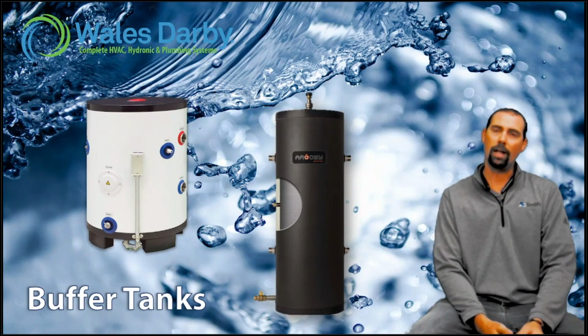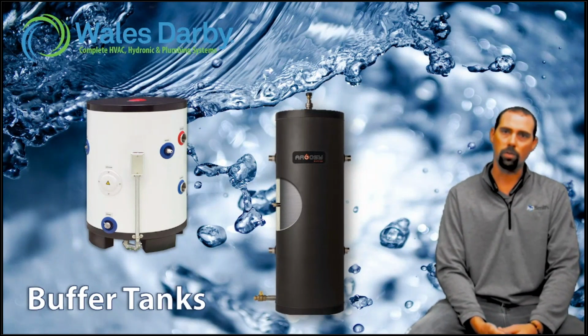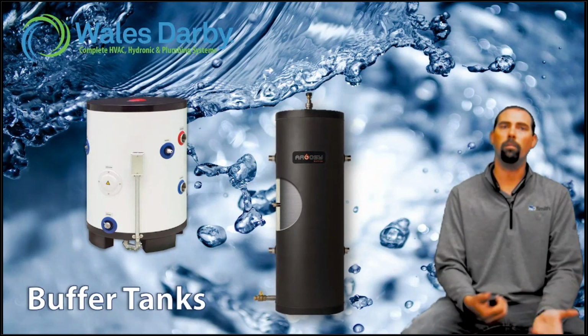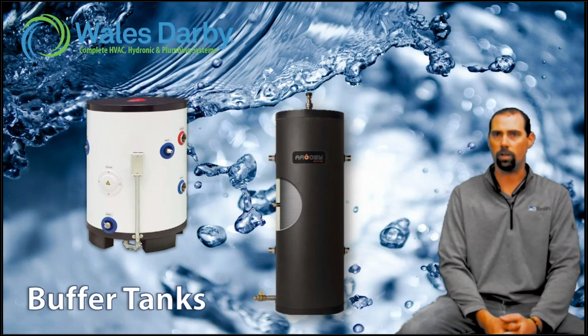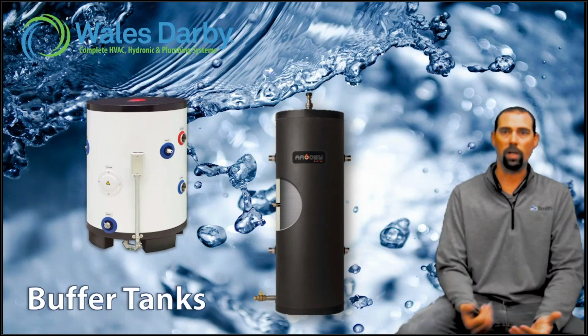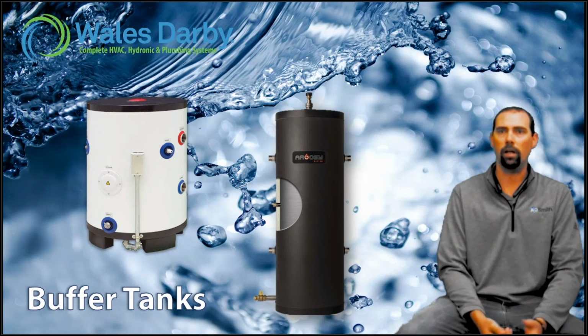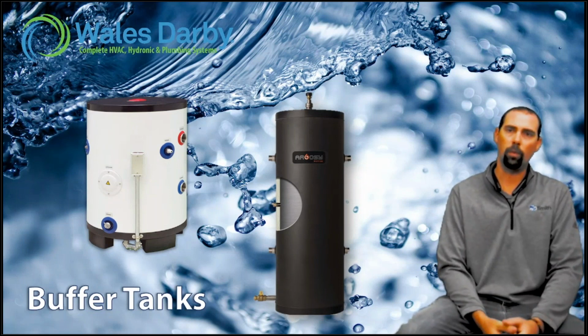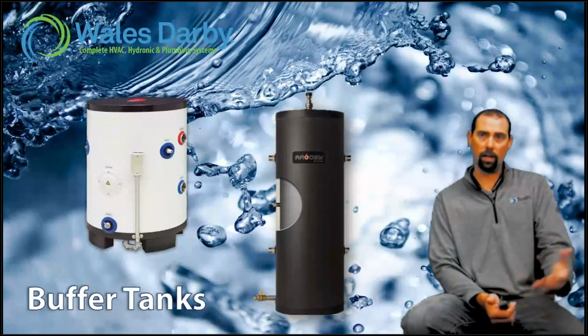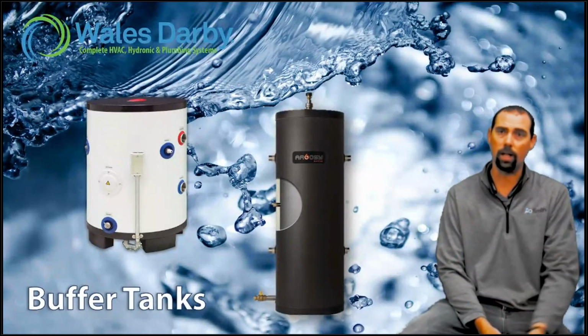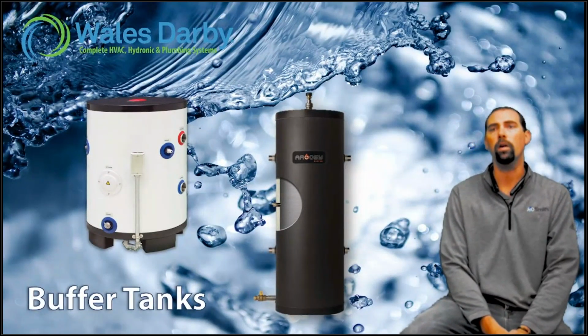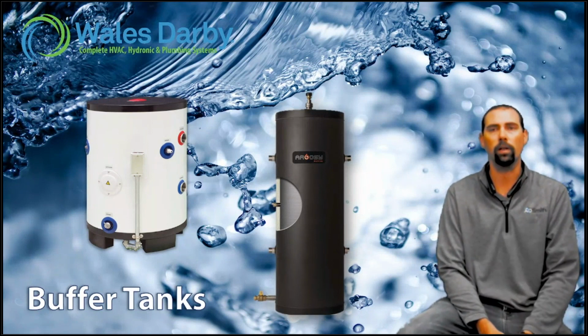One of the nice things with the new inverter technology is we don't have to go with as big a buffer tank in some residential applications, because we can ramp the outdoor unit down to match our loads. That's something we weren't able to do in older systems, so we had larger buffer tanks. Having more storage isn't a bad thing if you've got the space for it, but that's all a buffer tank really is.